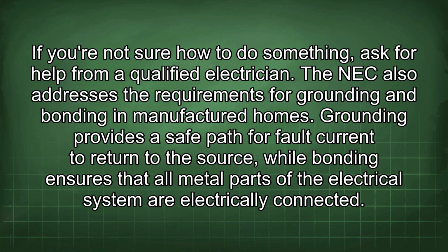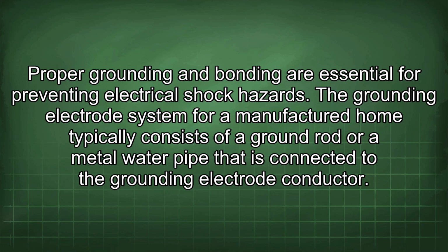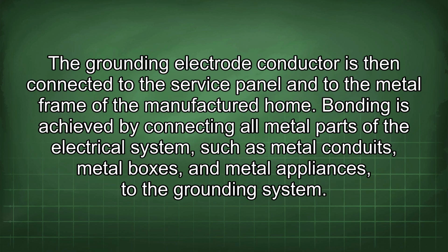The NEC also addresses the requirements for grounding and bonding in manufactured homes. Grounding provides a safe path for fault current to return to the source, while bonding ensures that all metal parts of the electrical system are electrically connected. Proper grounding and bonding are essential for preventing electrical shock hazards. The grounding electrode system for a manufactured home typically consists of a ground rod or a metal water pipe that is connected to the grounding electrode conductor. The grounding electrode conductor is then connected to the service panel and to the metal frame of the manufactured home.